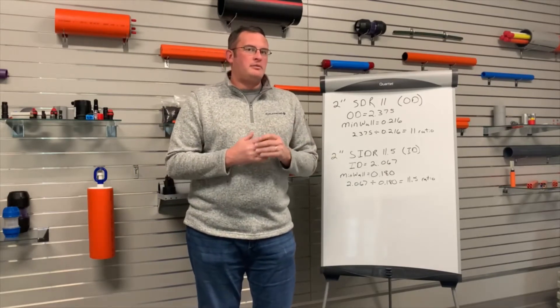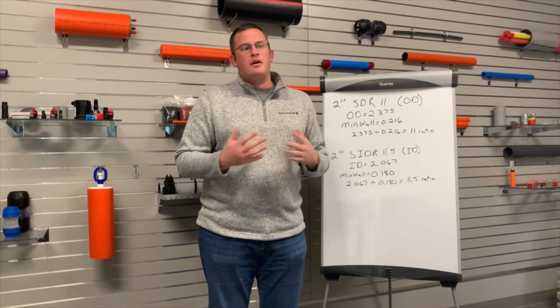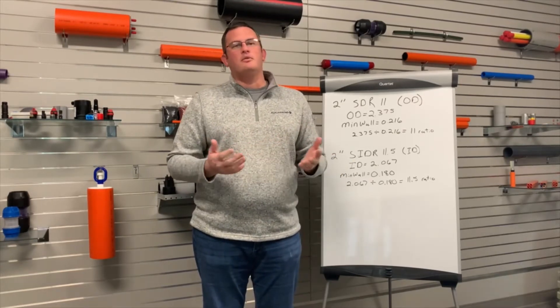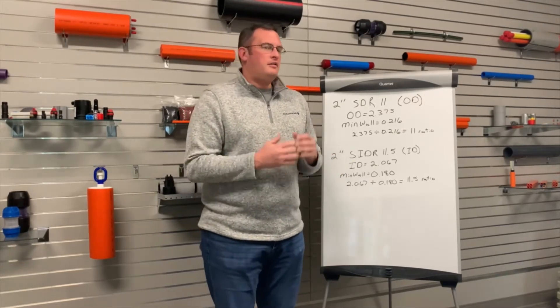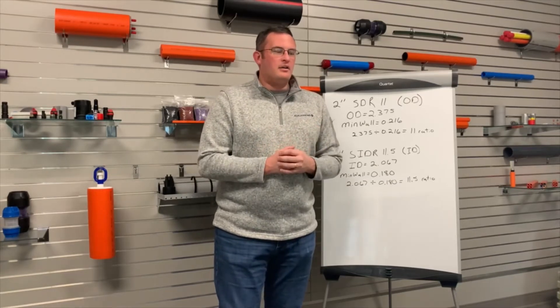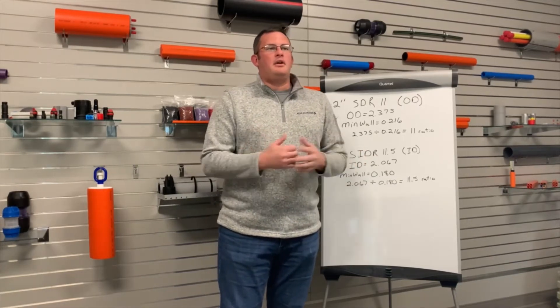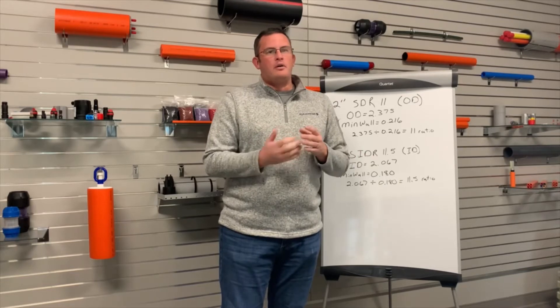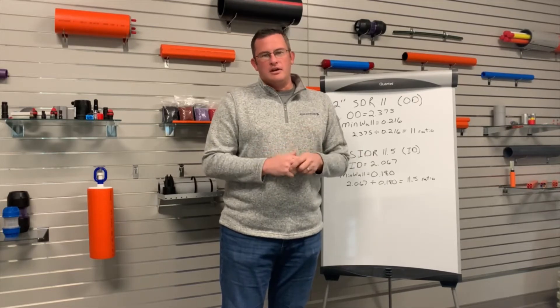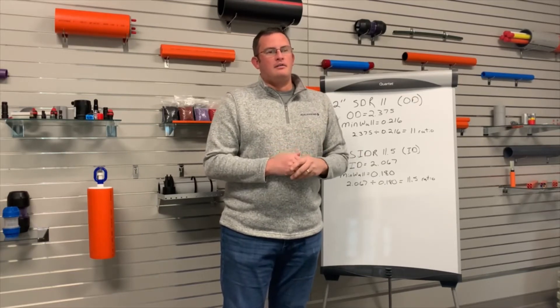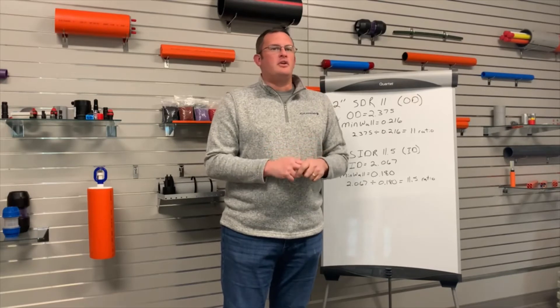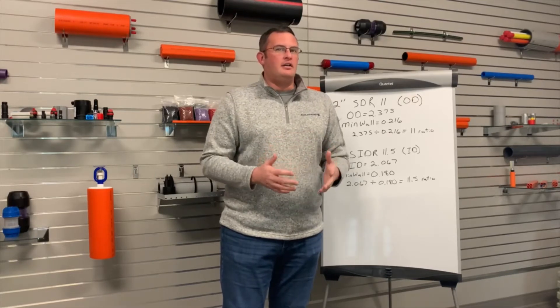The other two that I'll spend just a few seconds explaining — the calculations, why they are, and how those relationships or ratios work — are SDR and SIDR. SDR is developed as a ratio of OD to wall thickness, whereas SIDR is a similar ratio, however it's constrained to the ID of the pipe.